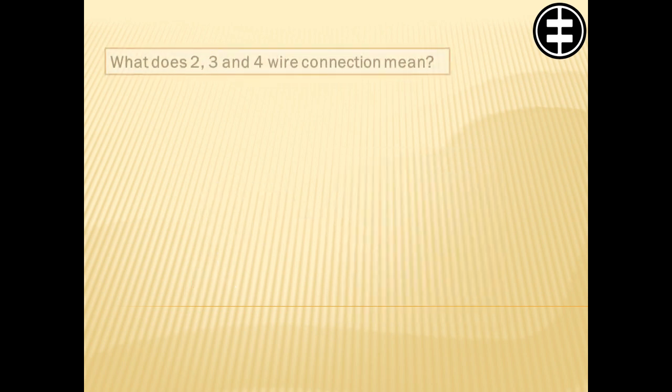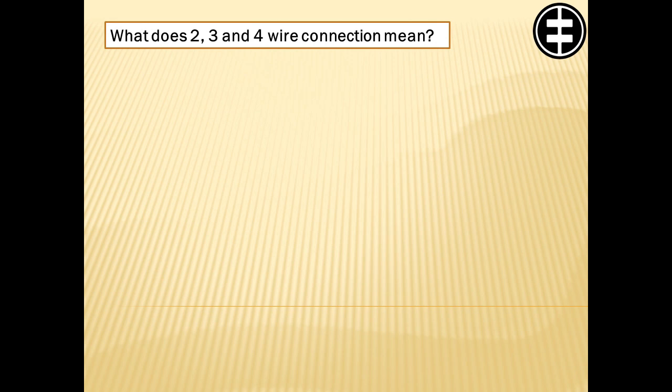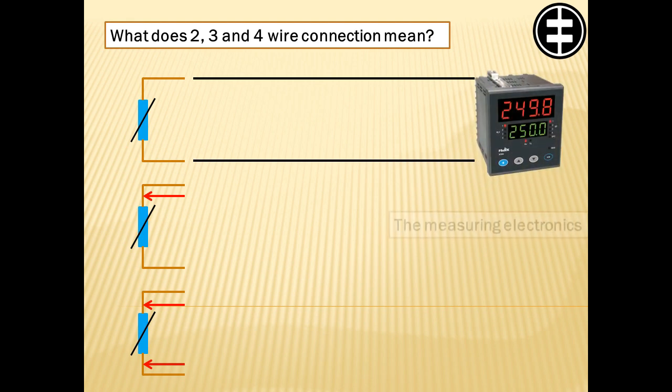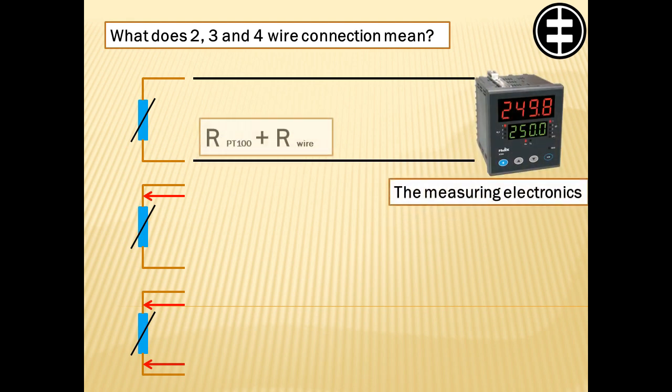What does 2, 3 and 4 wire connection mean? A resistance temperature detector, RTD, can be connected with 2, 3 or 4 wires. The 2 wire connection needs only 2 wires, but then the measuring electronics is measuring also wire resistance, which is not desirable.